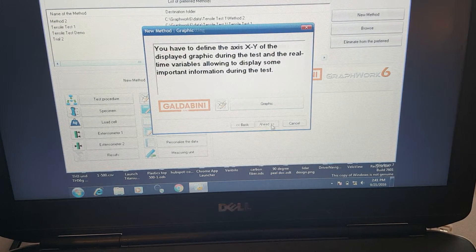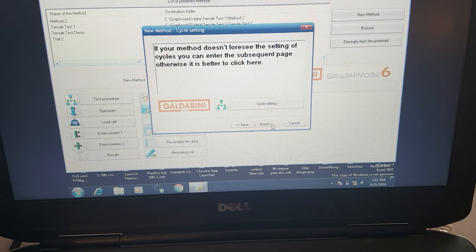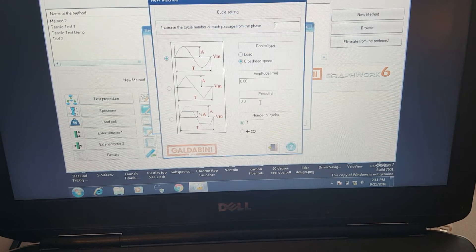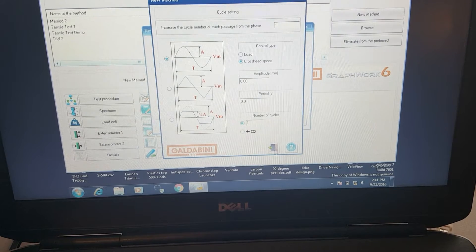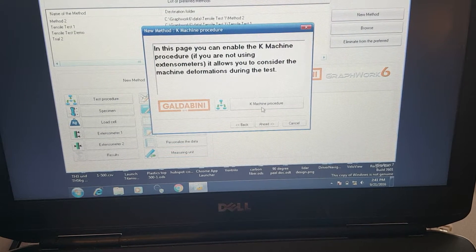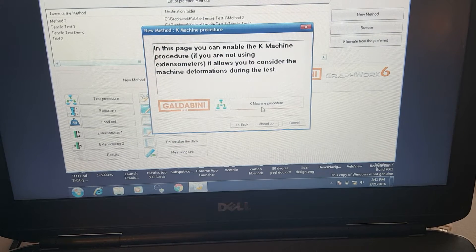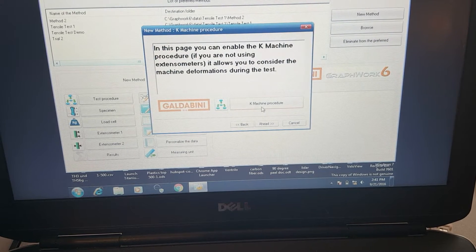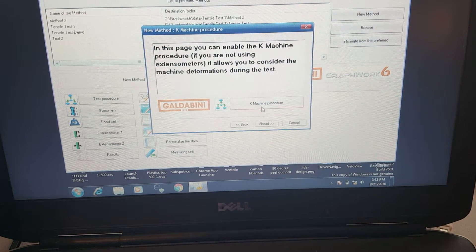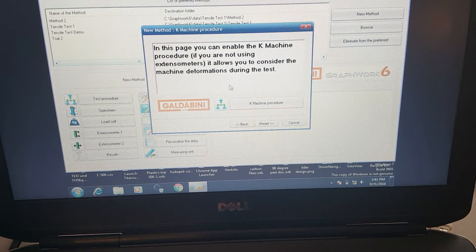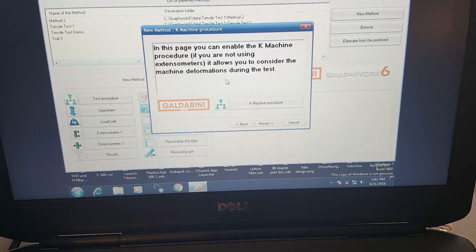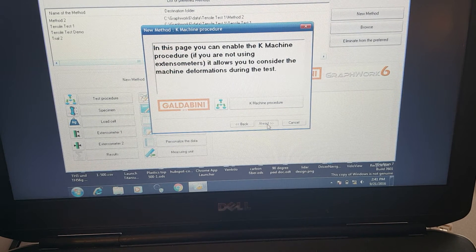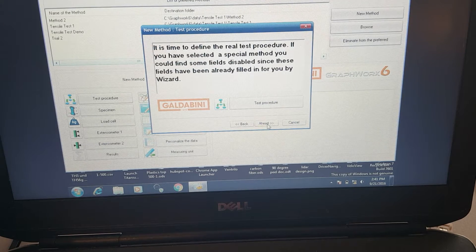We have our graphs all set up. Here we can set multiple cycles if we're doing some sort of cyclic testing. This is for the K-machine procedure for setting a constant for the deformation of the physical machine. This is really only needed for compression testing, so we'll skip that for today.